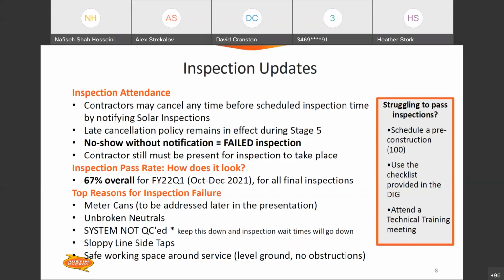Line side taps installed in a poor manner - our inspectors are catching those as well. Also make sure you have a safe working space around the electric service, installing over level ground and not over a grade with obstructions around the electrical equipment. Make sure to refer to the required clearances as listed in our design criteria and also our distribution interconnection guide.